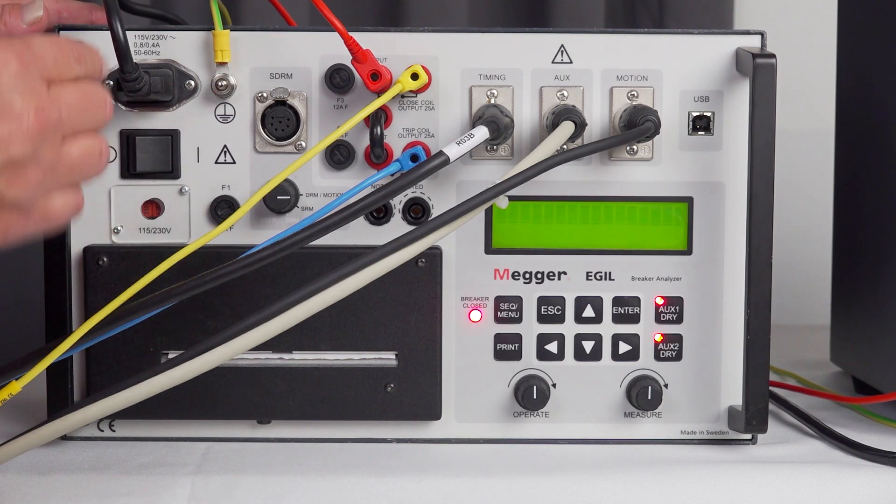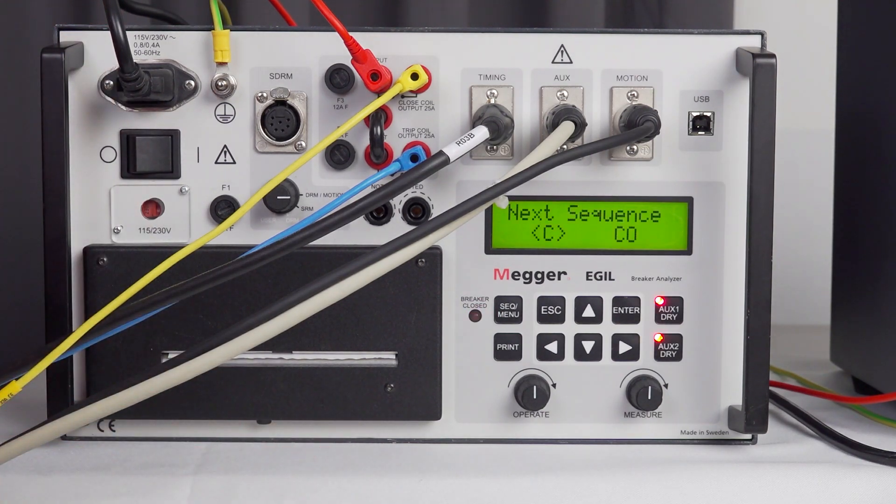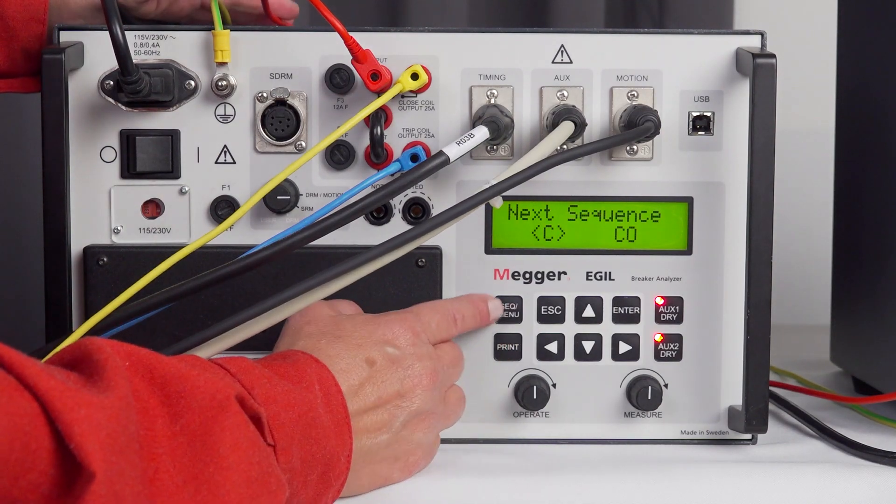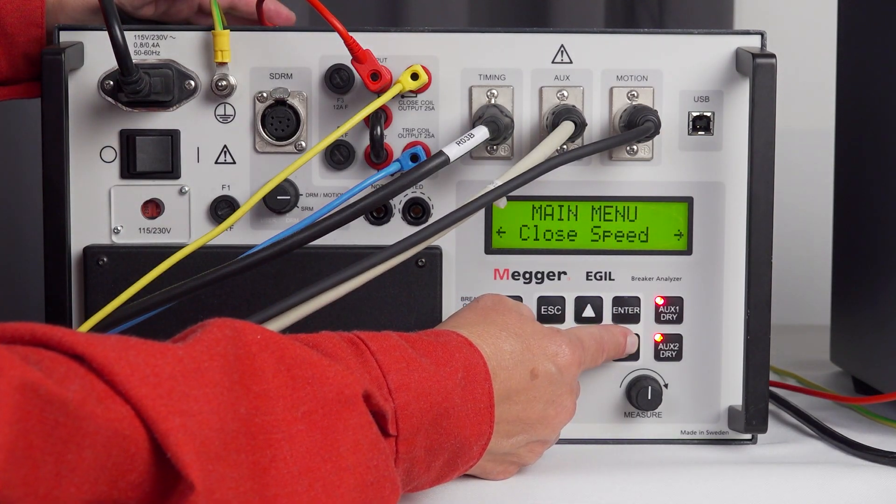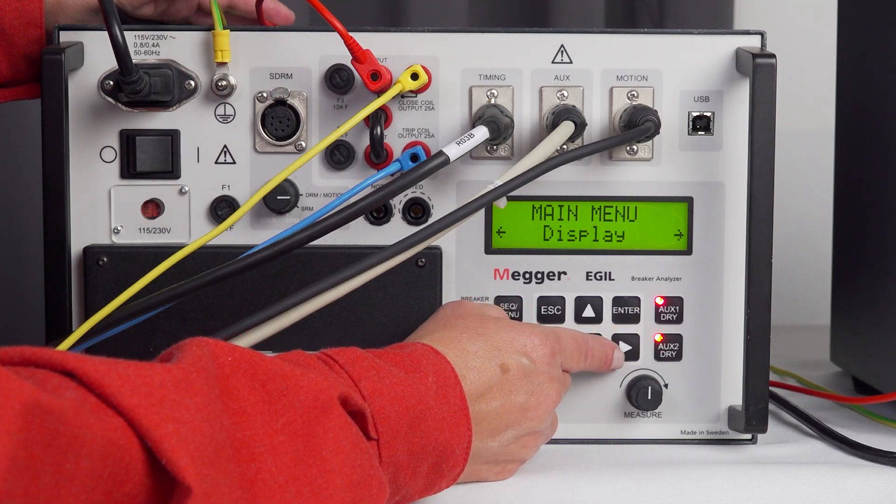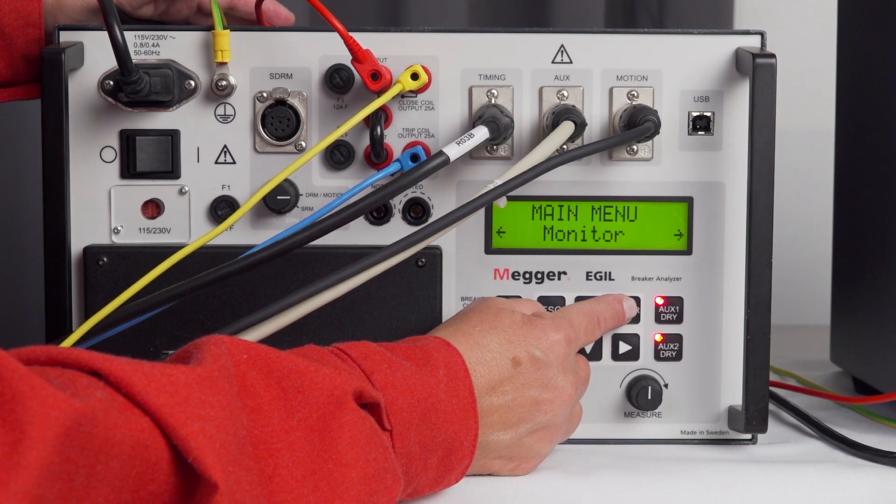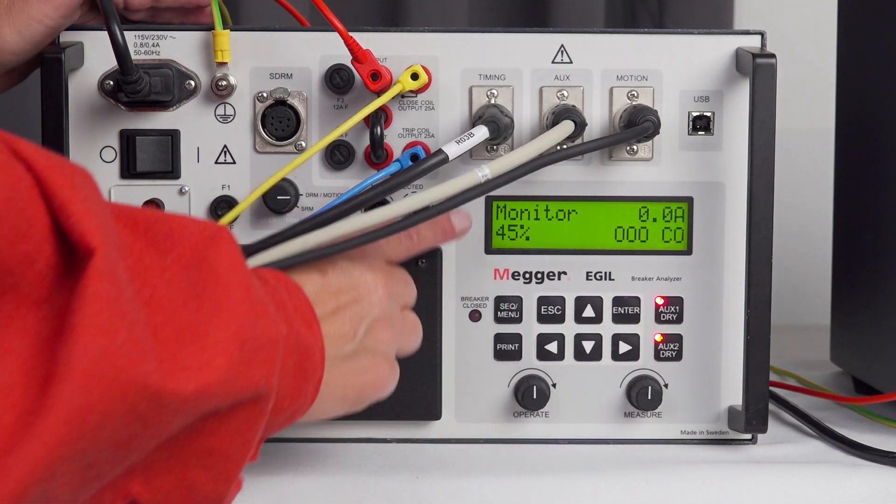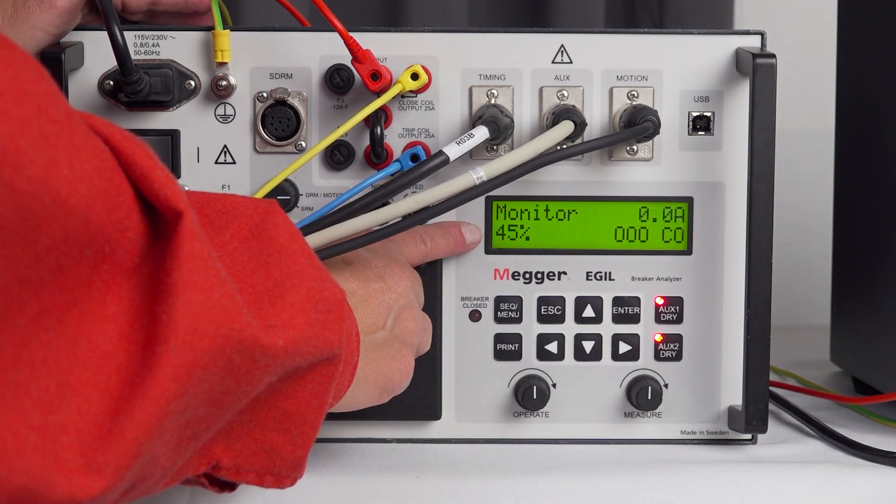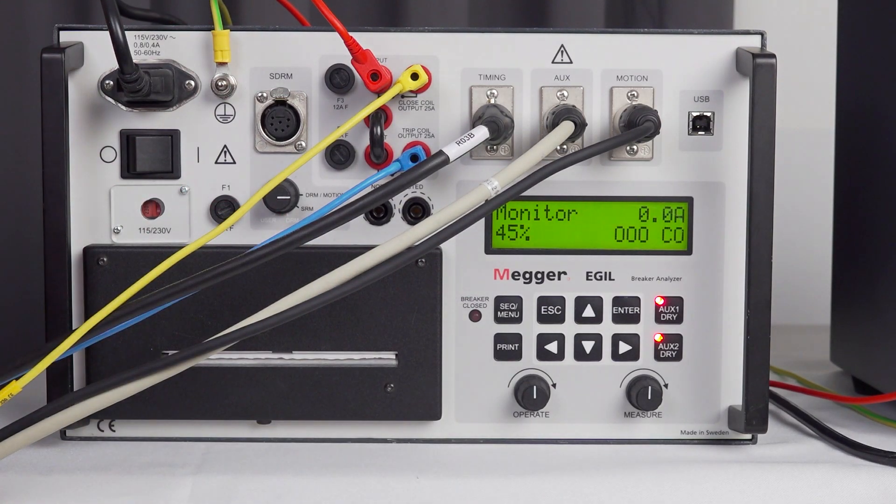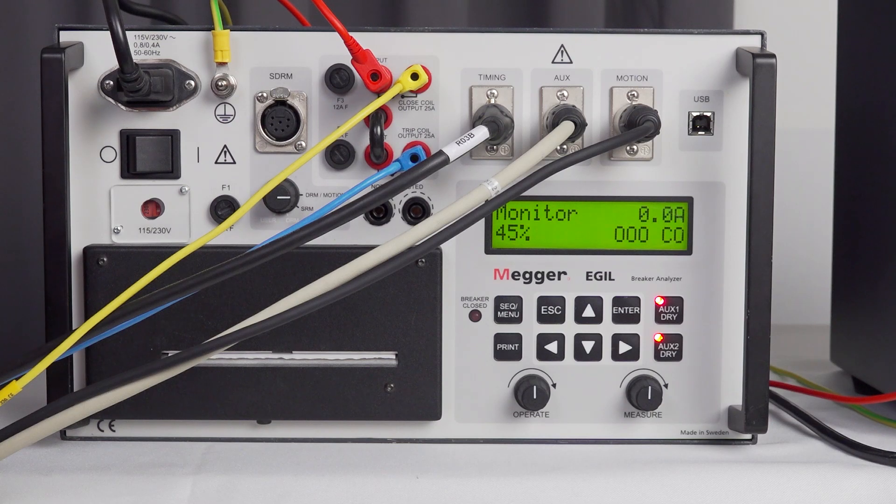I turn on the instrument to check that the transducer is in correct position. I go to menu and I move to monitor. Here I can see that the transducer is on 45%. I need it to be between 40 and 60%. And if it's not correct, I need to loosen the flex coupler again and turn the transducer a little bit so it is in this region. That is because the transducer has a gap and we want to avoid that gap during the measurement.